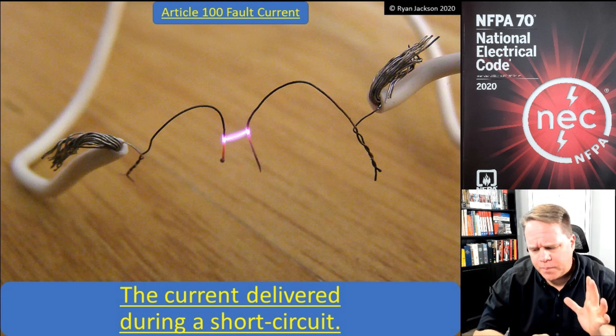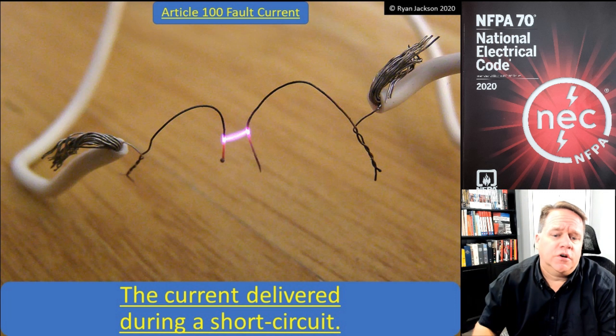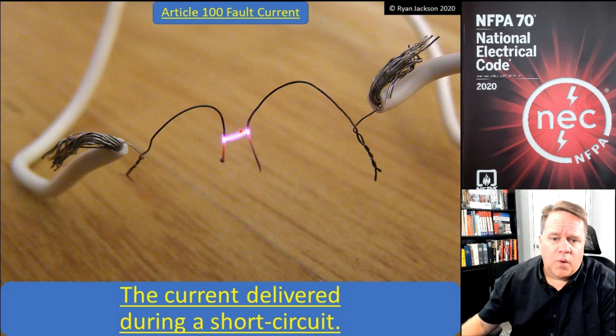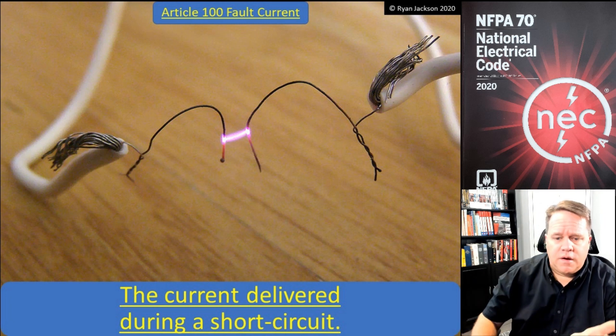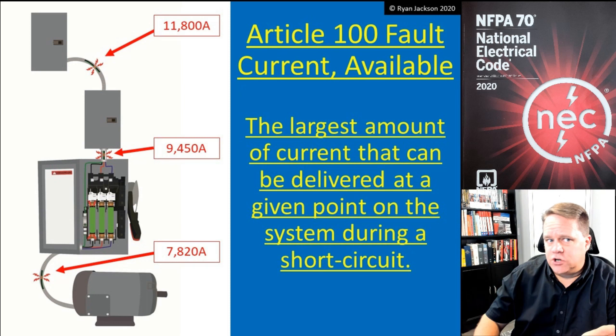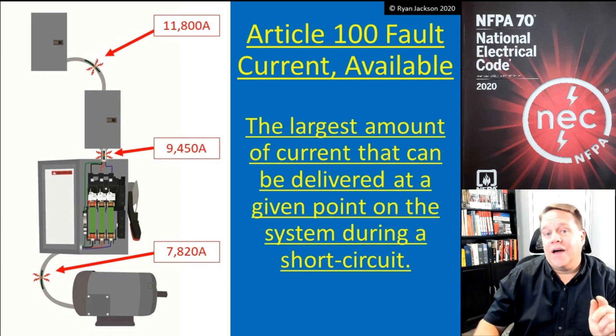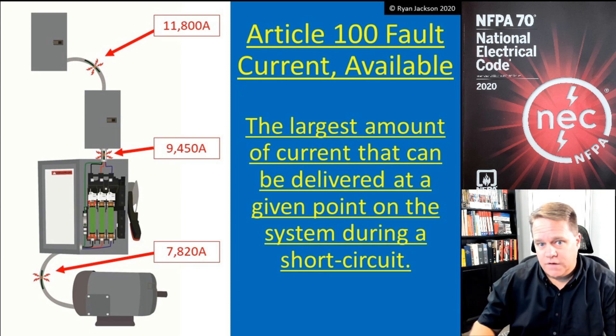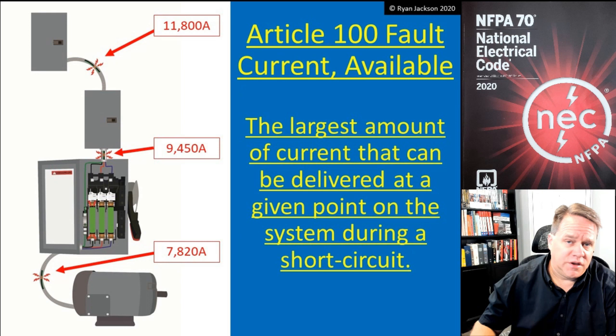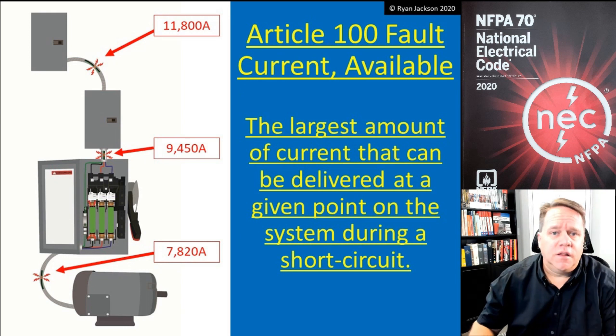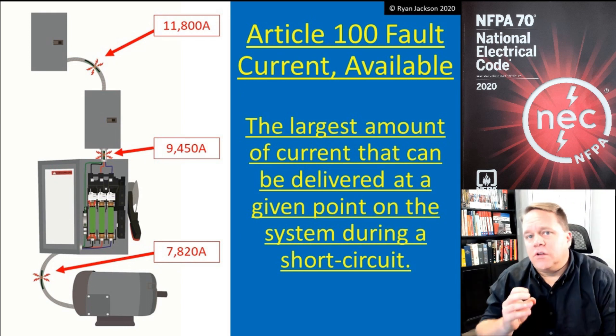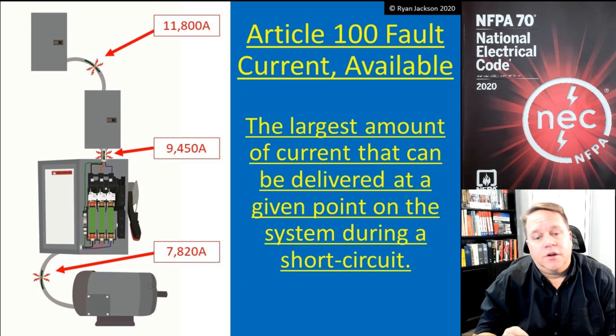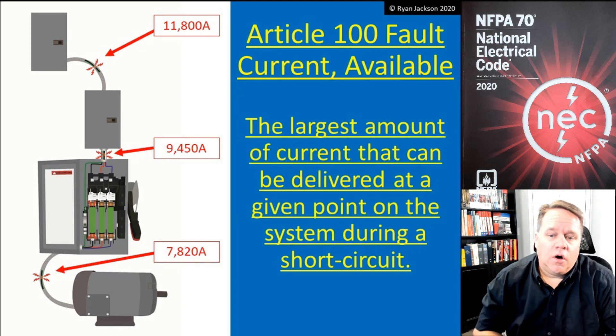Fault current is the current that's delivered during a short circuit — however much current flows when you bang those two wires together is the fault current. We added that definition really so that we could add this next one, which is critically important: available fault current. That's the largest amount of current that can be delivered at a given point on the system during a short circuit.